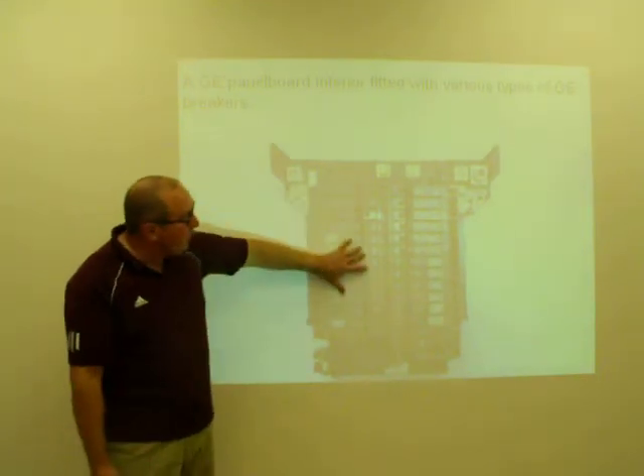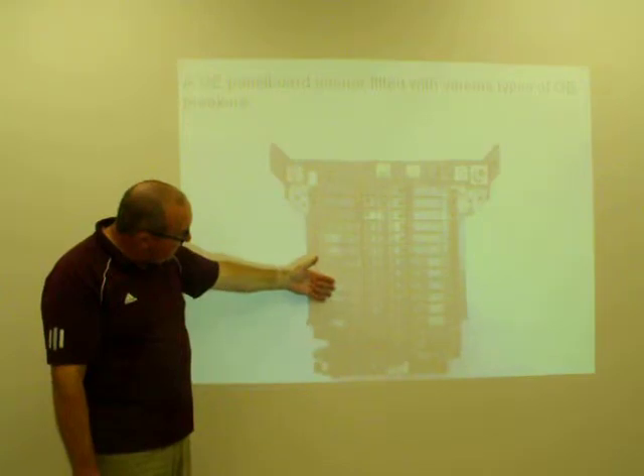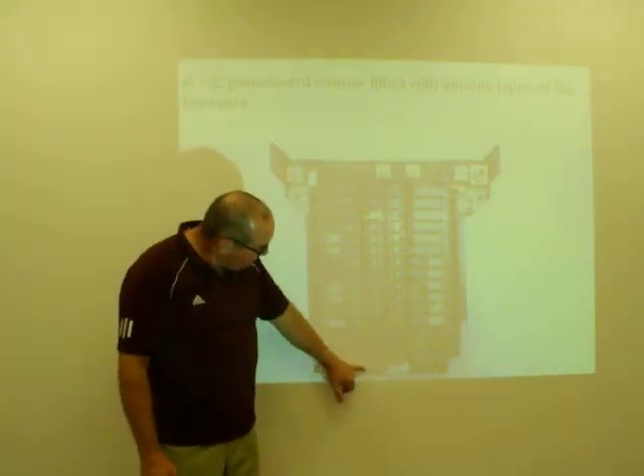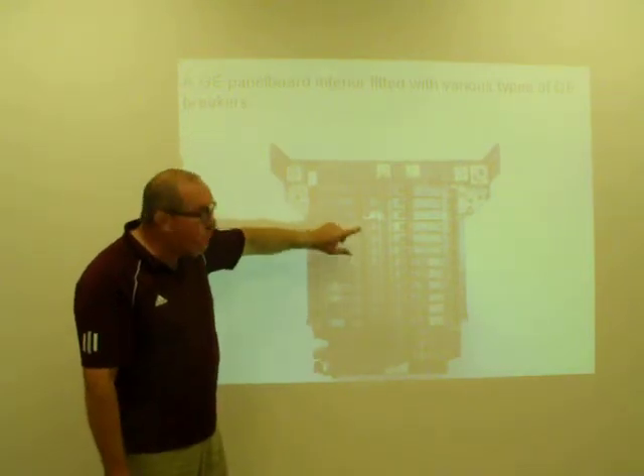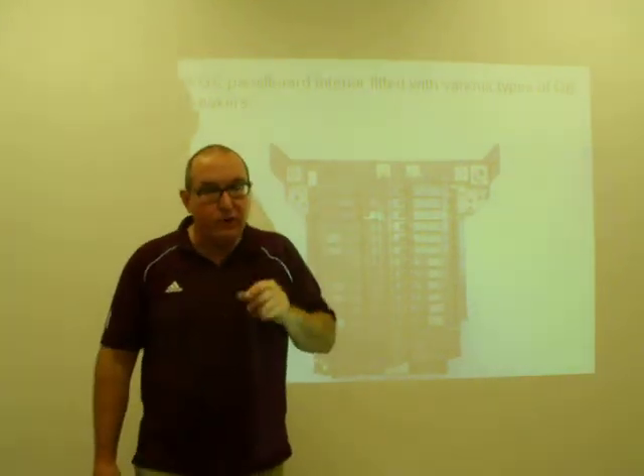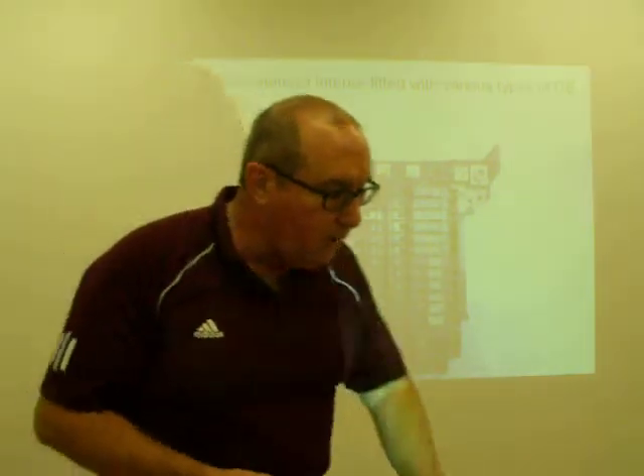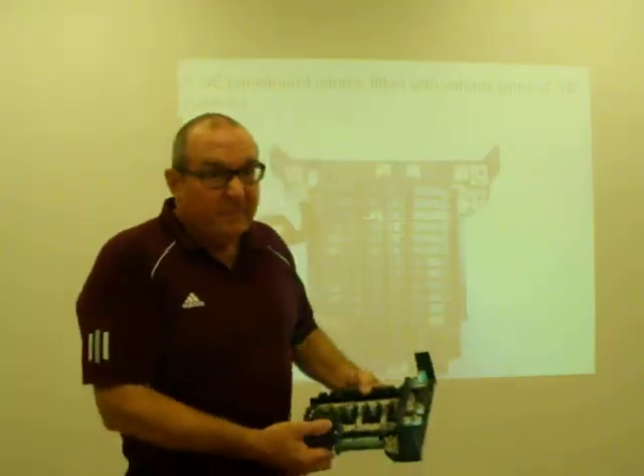This is again a picture of the interior. This is showing it essentially fully loaded with GE breakers. The majority of these breakers are half-size or slim breakers. There's a full-size breaker. A number of these breakers are 2-pole breakers. They will only fit in certain places on this panel board as well. Because the idea of a 2-pole breaker is that it is meant to provide a 240-volt circuit.